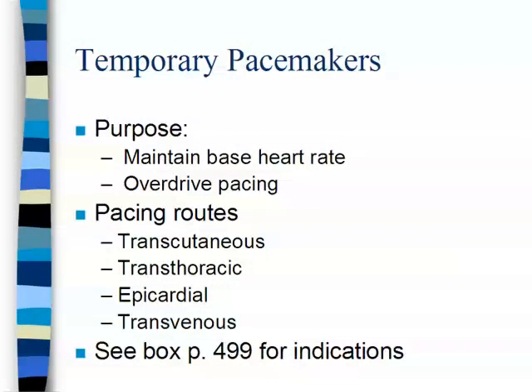Now, the wire that goes in is usually bipolar, in case one breaks, but it can be unipolar. Unipolar is more sensitive to extraneous signals like IV pumps and muscle movement, so that's another reason they tend to use the bipolar leads. Your epicardial, as I said, is used after surgery because you've got the chest open and you can just screw it in where it needs to go. But you need to make sure you have somebody who knows what they're doing, because if they screw it through a coronary artery, they've just caused a heart attack. There is a box on page 499 for your indications and for your components of your temporary bipolar pacing catheters. On page 502, you'll find your external generators, a picture of them.